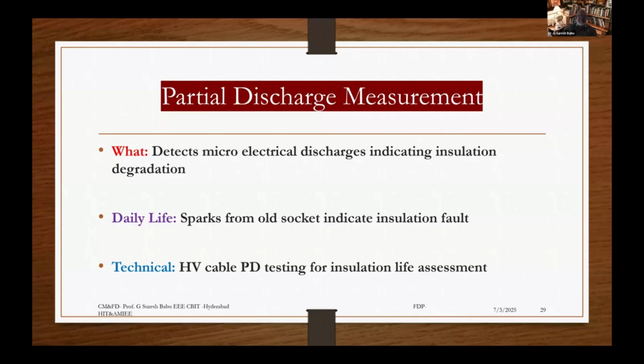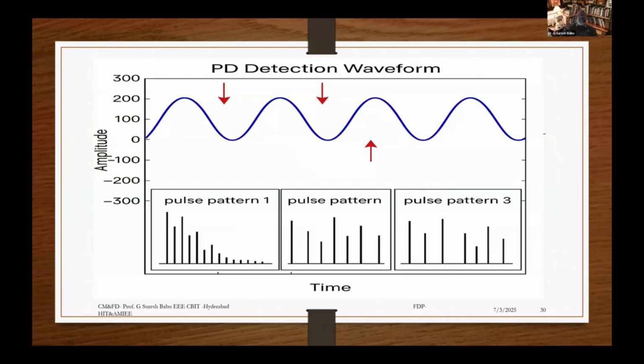A daily life example is a spark from an old socket, which indicates insulation failure. A technical example is high voltage cable partial discharge testing for insulation life assessment. Especially in transformer oil, we do this partial discharge test. See, this is a partial discharge detection waveform, amplitude versus time. It's not any case study, please.